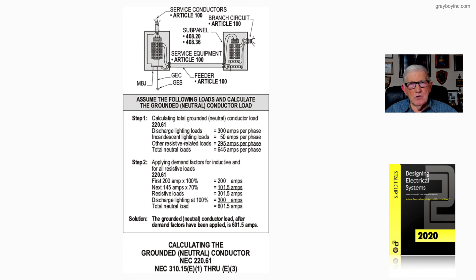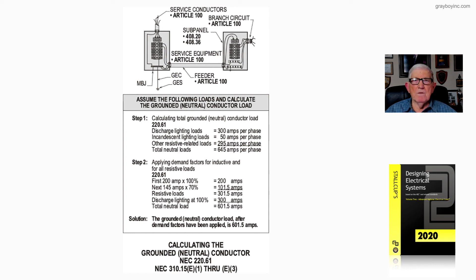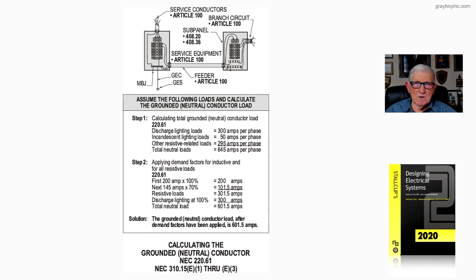Adding the resistive and inductive loads together, the neutral load is 601.5 amps instead of 645. The grounded neutral conductor load after demand factors have been applied is 601.5 amps, after separating resistive loading from inductive loading. That is what 220.61 is asking the designer to do, and that is what this illustration is illustrating to the user of the NEC.